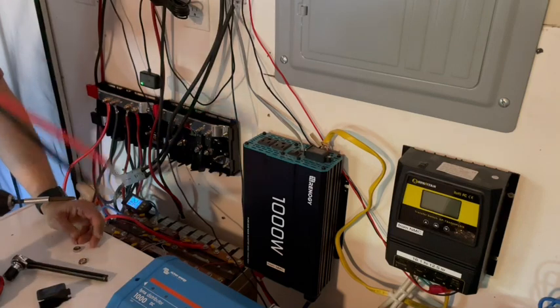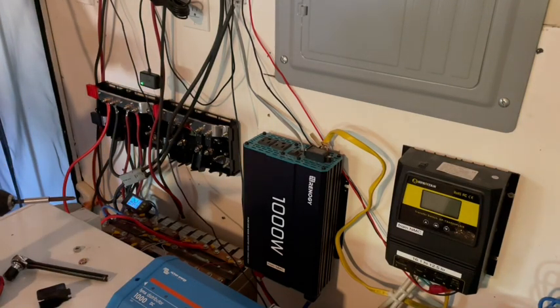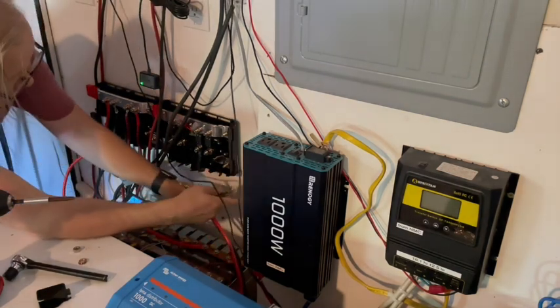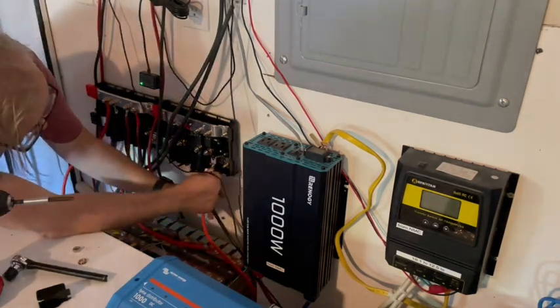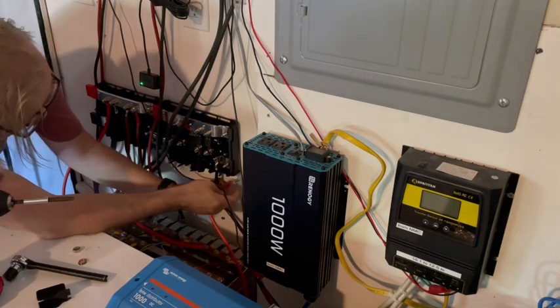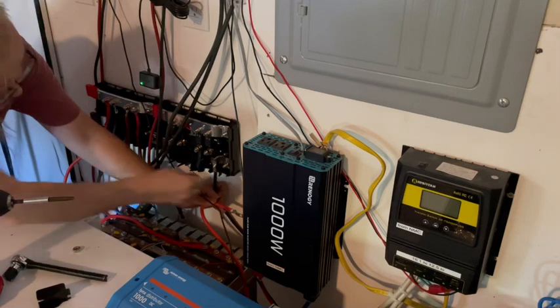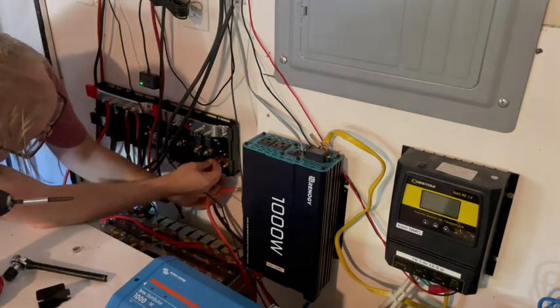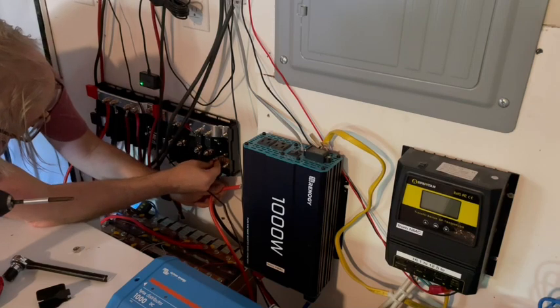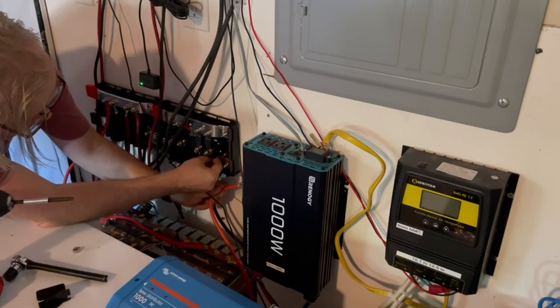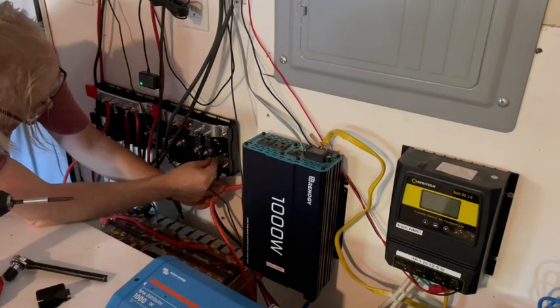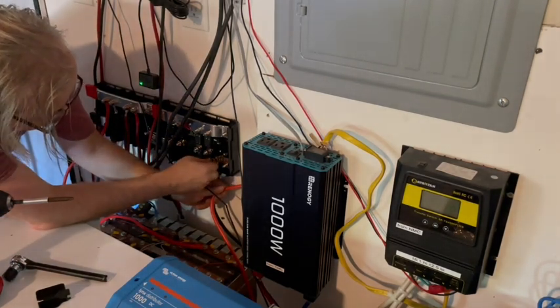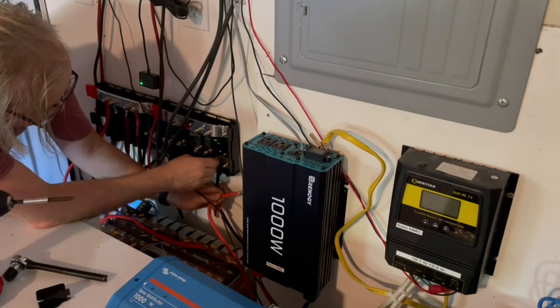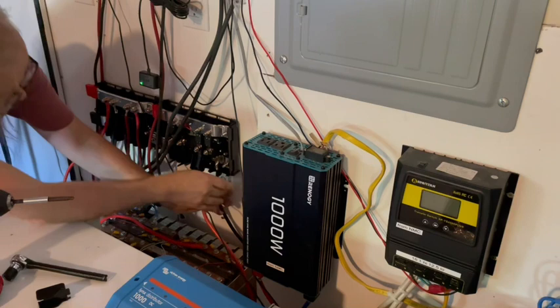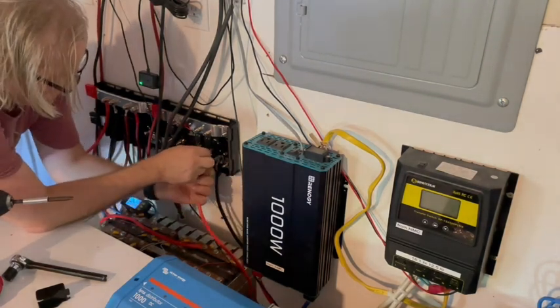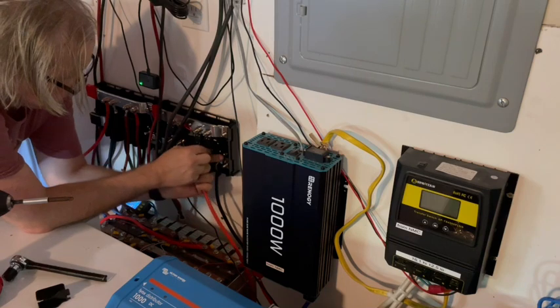There might be unknown high current bursts that might exceed 250 amps for a small fraction of a second. And so even though in theory that's not supposed to happen, in reality that may actually happen. So a fast blow fuse might actually pop even though all the components are meant to draw less power, and even though the inverter is only a 1 kilowatt inverter, its capacitors for inrush current might generate power bursts which are a couple kilowatts.